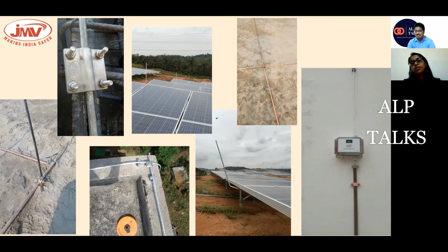As per the National Building Code, the maximum height we can go above the panel is 0.5 meters only. So these air terminals are L-shaped, and they are only 0.5 meters above the panels. As you can see in this picture, there are a number of air terminals installed at every row. This happens as per IEC 62305 and the National Building Code, according to which we have to design the system. So in this manner, we do this.